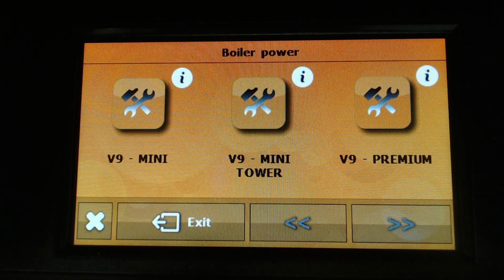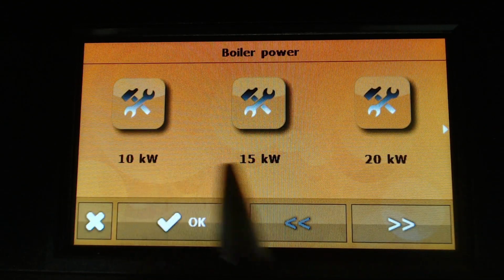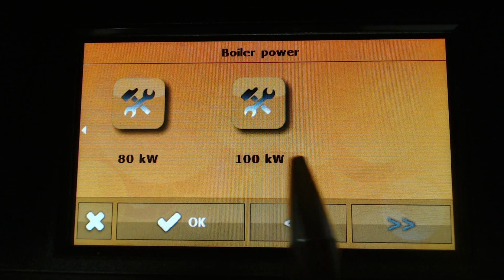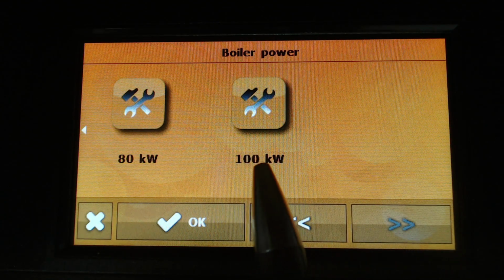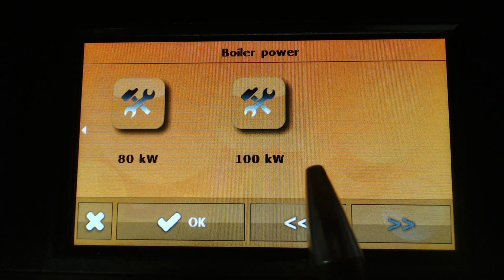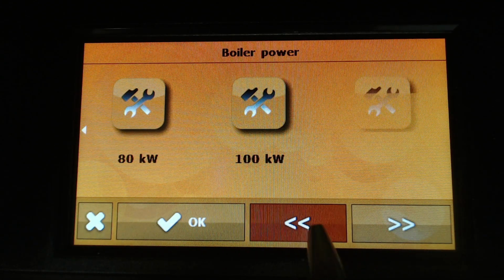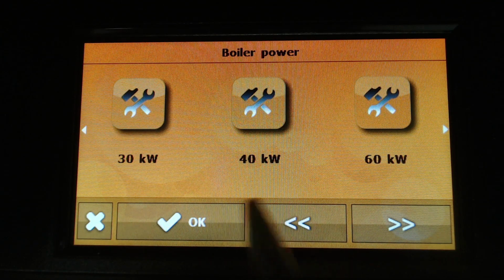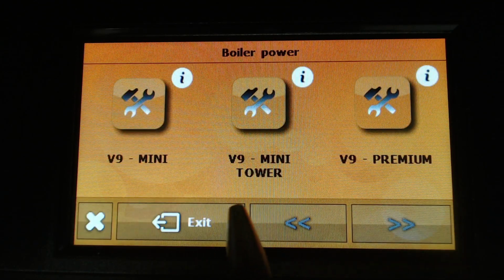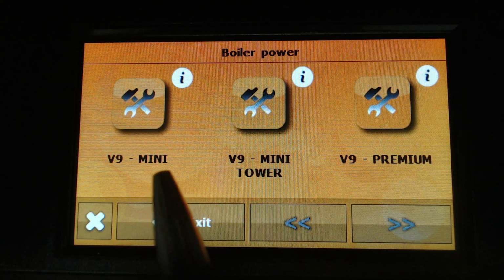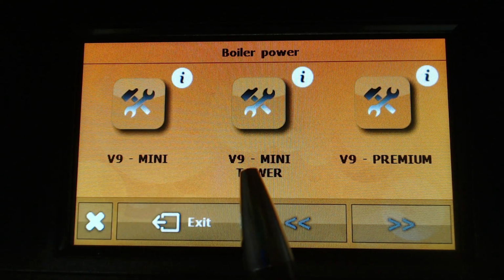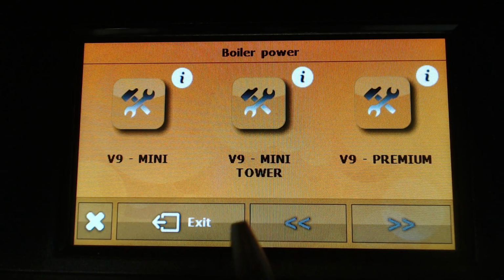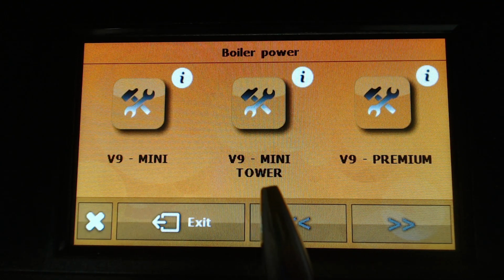And you see that before there was only the V9 Premium version, and inside there was a selection from 10 to 200 kilowatt. In this case it's 100 kilowatt maximum, because I have a slightly older version of the software, but basically V9 Premium is a boiler from 10 to 200 kilowatt. Right now there is a new selection for Biopal V9 Mini and Biopal V9 Mini Tower. Each selection will save different values inside the service settings. It depends, of course, on the power and type of the boiler.